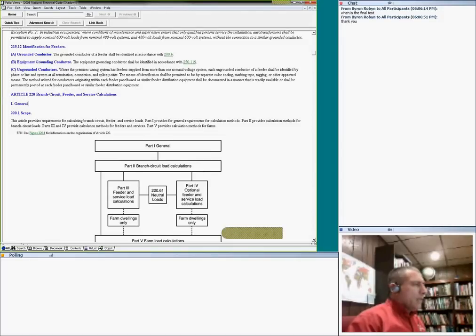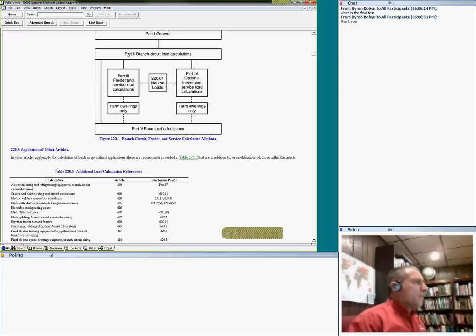No question asked about it. It talks about the branch circuits first, how to do branch circuit calculation, then it moves to the feeder. As you guys can see, it moves to the feeder in two locations. Number one, it does the feeder for farm dwellings, but this is the most important one right in here. There is optional. We go to optional if you want to, but I personally always use the standard method. And also the neutral, you can derate the neutral. So you can do calculation for feeder and service under part 3 and the neutral.